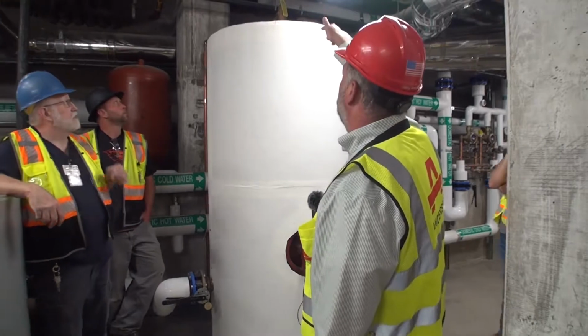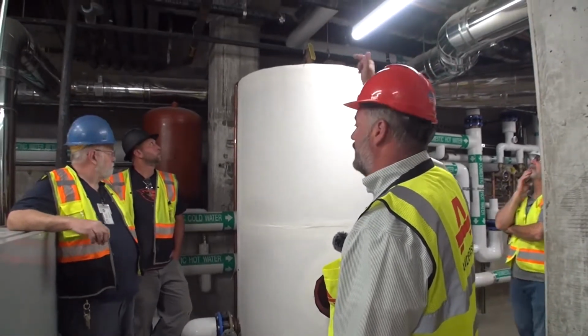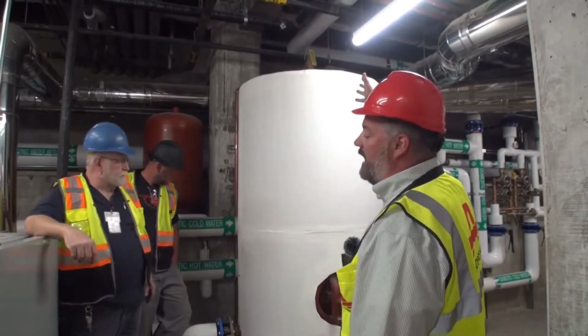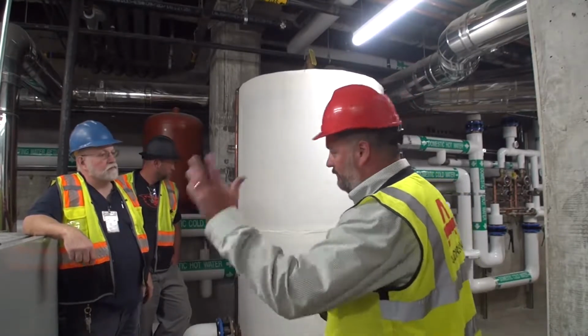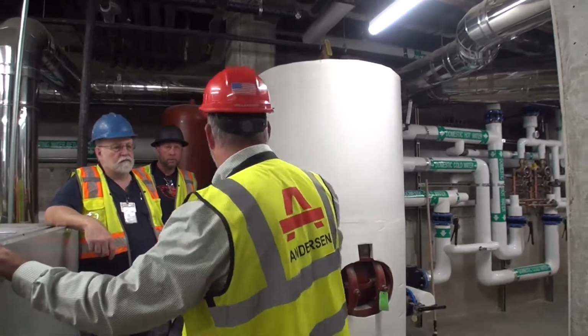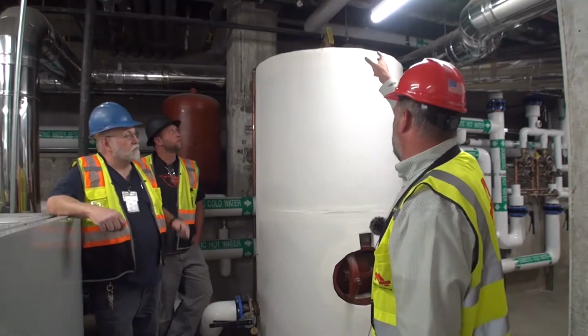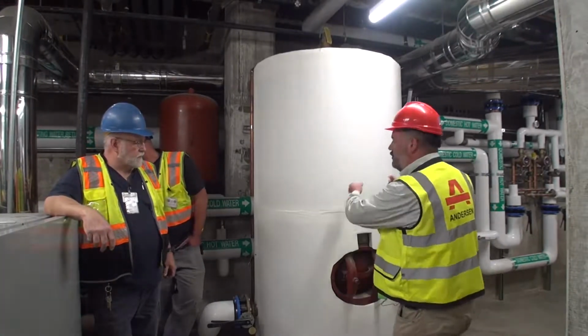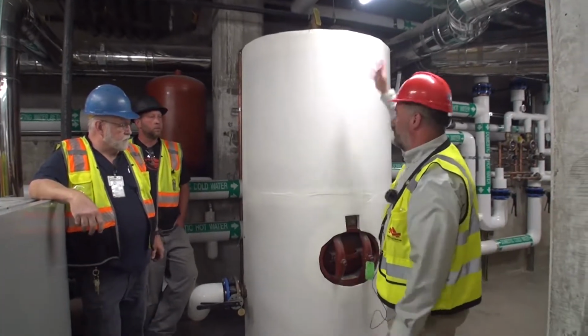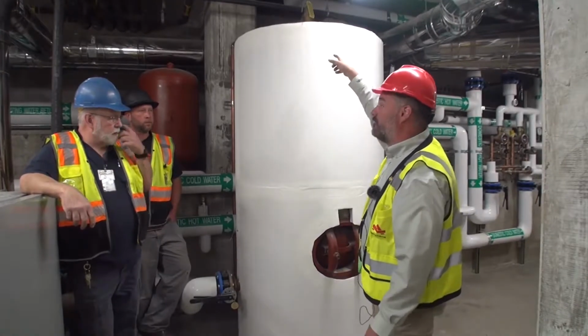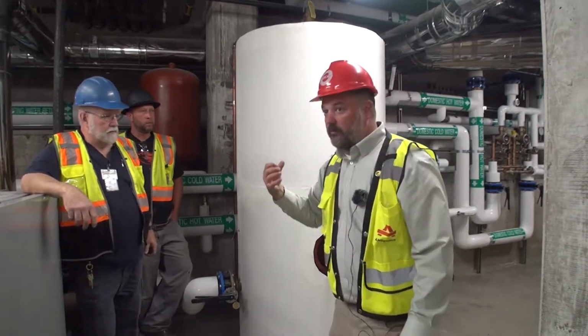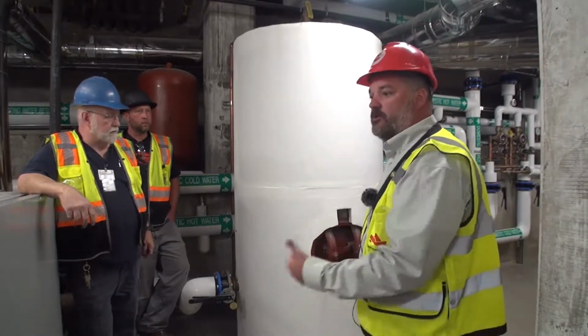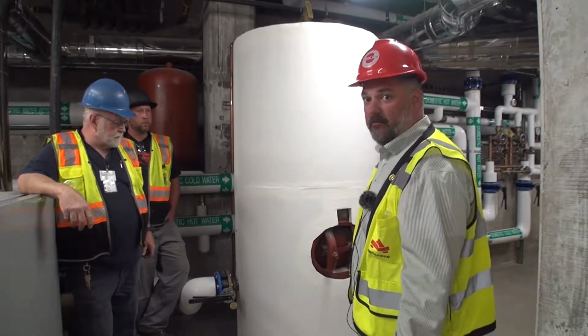On the very top of that, you've got your boiler relief valve. That boiler relief valve is a safety valve that, God forbid, if these boilers run wild, we've got a pressure relief valve there that if this thing's building too hot a temperature, it's what it's meant to do, we're going to start dumping out of there. So if that starts dumping, and I mean full dump scalding water, we know we've got a temperature problem we've got to correct. It's a big time safety issue.